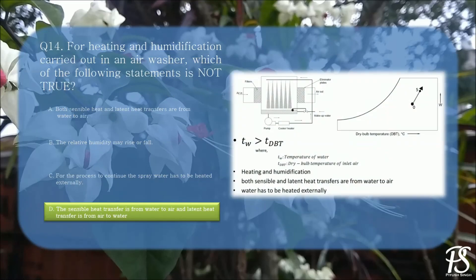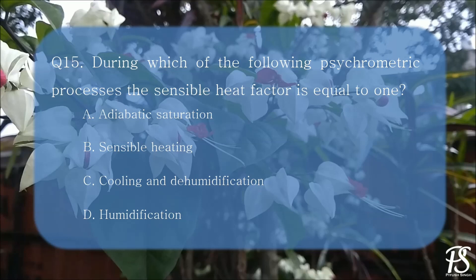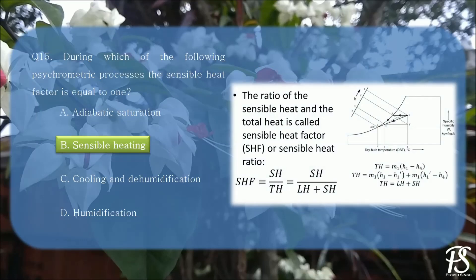This figure shows the process. During which of the following psychrometric processes is the sensible heat factor equal to 1? A. Adiabatic saturation, B. Sensible heating, C. Cooling and dehumidification, or D. Humidification. The correct answer is sensible heating. The sensible heat factor is the ratio of sensible heat to total heat (sensible plus latent heat). In a sensible heating process, the latent heat component is zero, hence the ratio equals 1. The sensible heat factor for sensible heating is 1, while it is 0 for humidification, and lies between 0 and 1 for cooling and dehumidification.